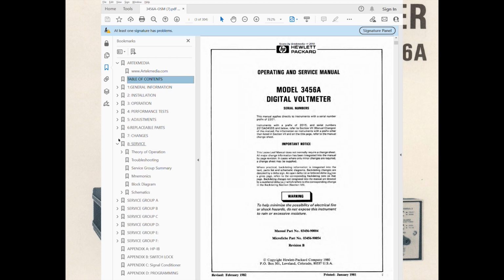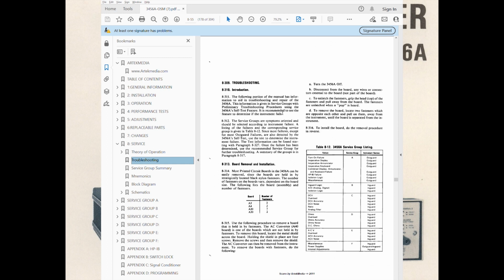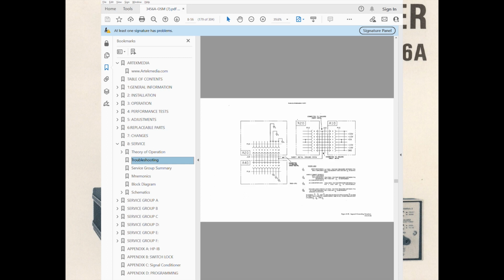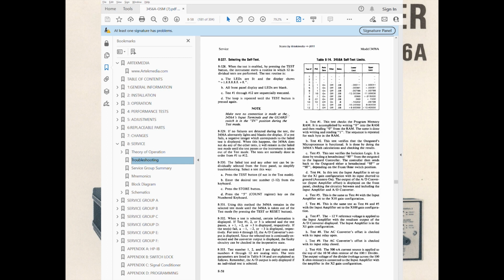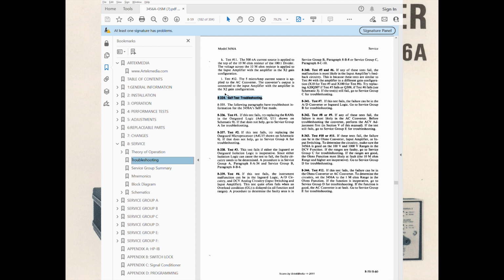Go to Section 8, Troubleshooting. Go to Section 8-334, Self-Test Troubleshooting. Down to 8-339, Test number 4. This is the error 4 that our unit exhibits. The description tells us it's either the in-guard logic, analog digital or DC volt circuitry. It also goes on to say the overload is often displayed during this failure. This sounds like our fault condition.